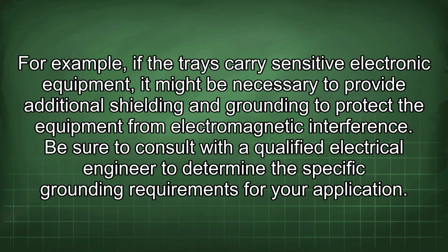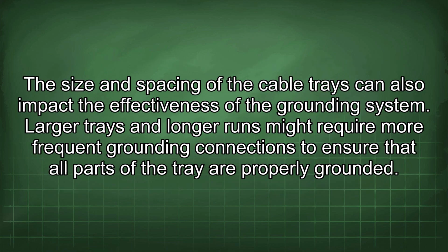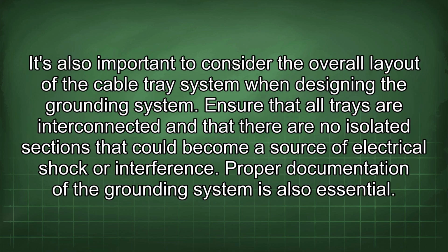For example, if the trays carry sensitive electronic equipment, it might be necessary to provide additional shielding and grounding to protect the equipment from electromagnetic interference. Be sure to consult with a qualified electrical engineer to determine the specific grounding requirements for your application. The size and spacing of the cable trays can also impact the effectiveness of the grounding system. Larger trays and longer runs might require more frequent grounding connections to ensure that all parts of the tray are properly grounded. It's also important to consider the overall layout of the cable tray system when designing the grounding system.